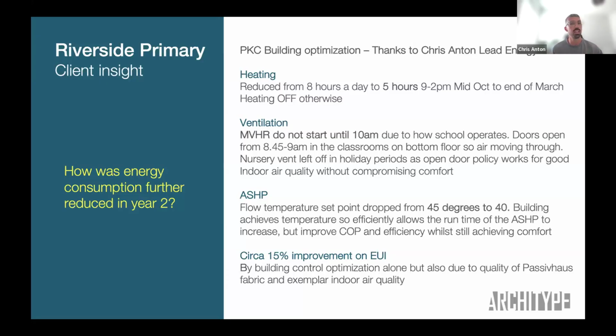We staggered it so the ventilation would come on an hour after the kids were in. We monitored the CO2 levels to make sure they didn't exceed the parameters, and they didn't. We managed to get a bigger heat gain within the building, while still getting the ventilation rates and air quality in the classrooms, which was really good.